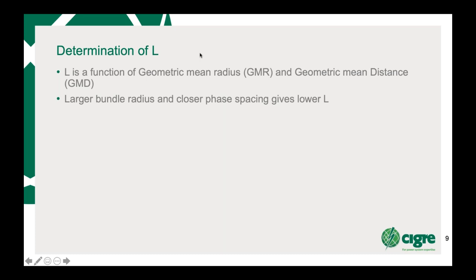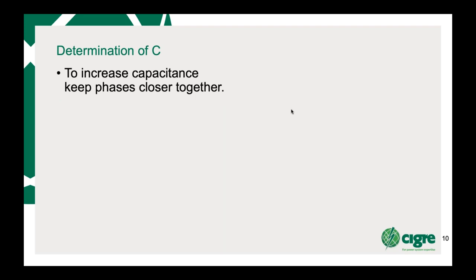at inductance. And inductance is a function of the geometric mean radius and geometric mean distance. Basically, you need to understand that the larger the bundle radius and the closer the phase spacing will give you a lower L. Now let's look at determination of C. Basically, what you need to understand with capacitance is, to increase capacitance, keep phases closer together.